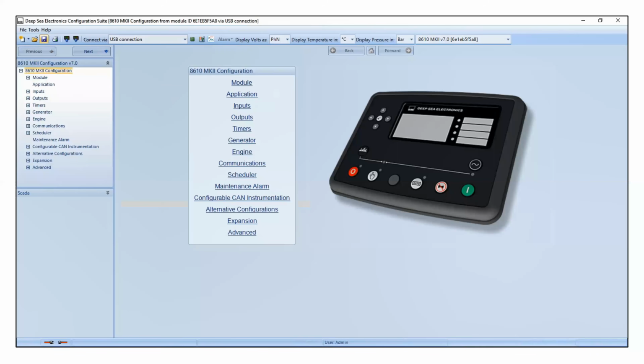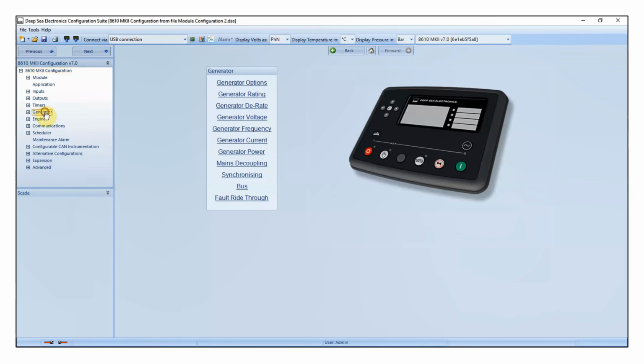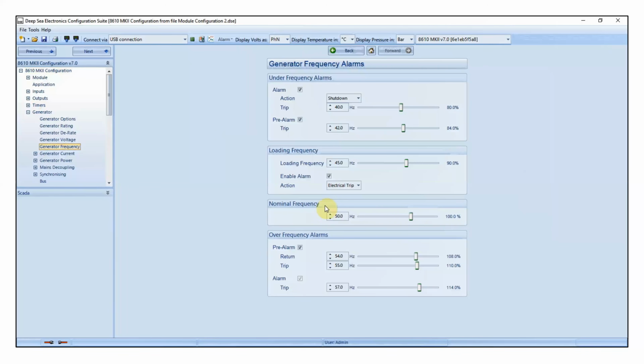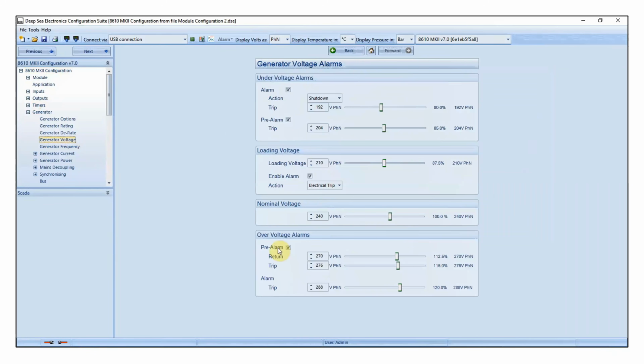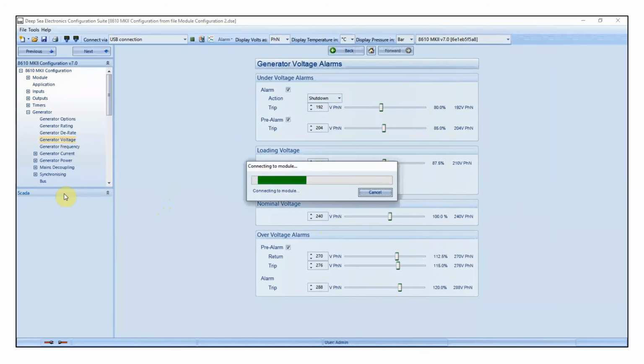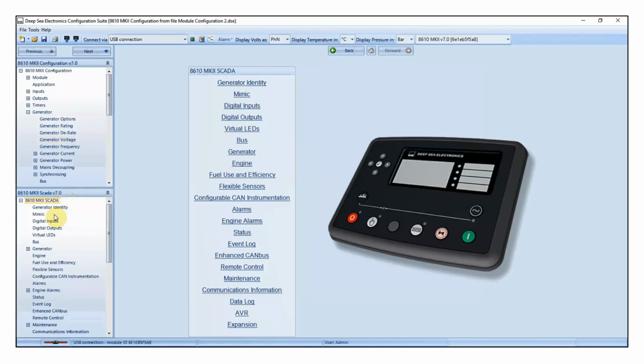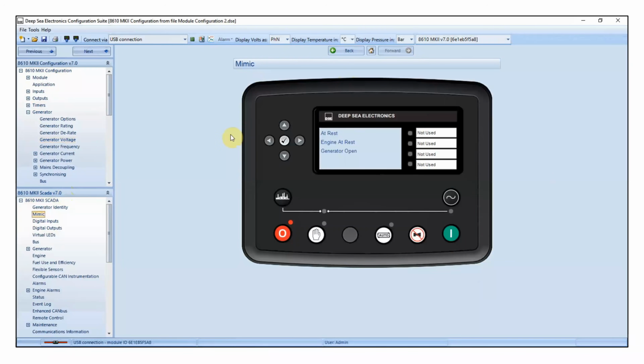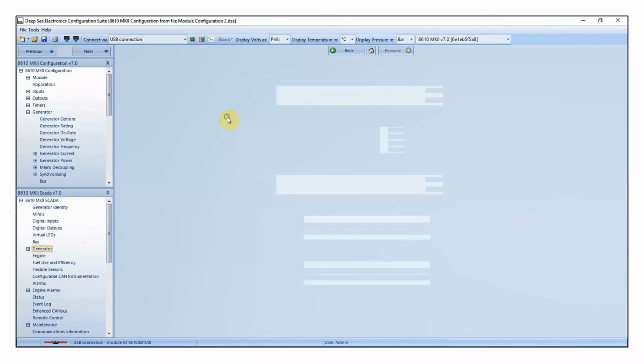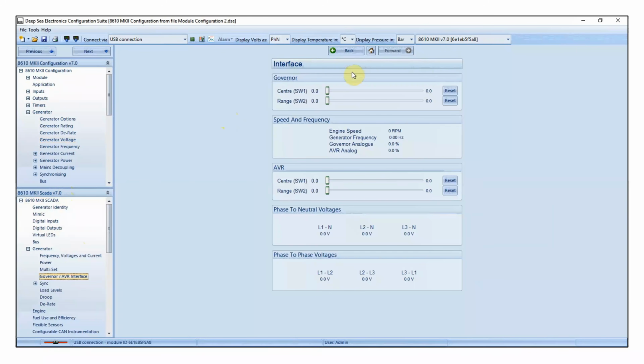The first thing we need to check in the configuration is the generator's nominal voltage and nominal frequency. We can do this by going to the generator section of the configuration and then to generator frequency. Here we can see what the nominal frequency should be, and here what the nominal voltage should be. I'll be doing all of this today in phase to neutral, though there's no problem doing it phase to phase. As part of the 4 steps, we'll also be connecting to the SCADA section. Just click on the bar and it will open. We'll be starting and stopping the generator using the mimic section of SCADA, but there's nothing wrong with using the physical buttons on the module. We'll also be looking at the switch 1 and switch 2 settings, which are found under the generator governor AVR interface, as you can see here.